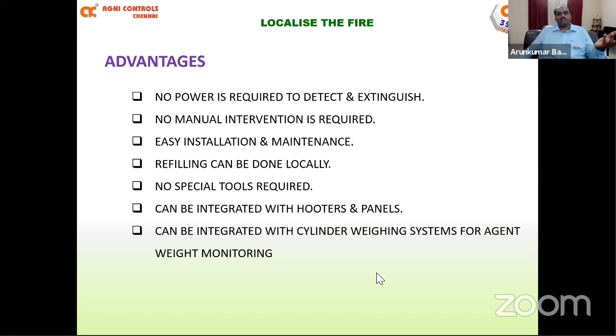Not many special tools are required, and the system can be integrated with hooters and other fire alarm panels to give audio-visual signals, because you need to know if there's a fire and that your system has extinguished it, so it can be informed to occupants or owners. We can integrate it using a pressure switch to hooters, panels, or centralized fire alarm panels, and also integrate it with a cylinder weighing system to monitor the cylinder contents. These are the advantages of the DIFA system, especially the carbon dioxide one.